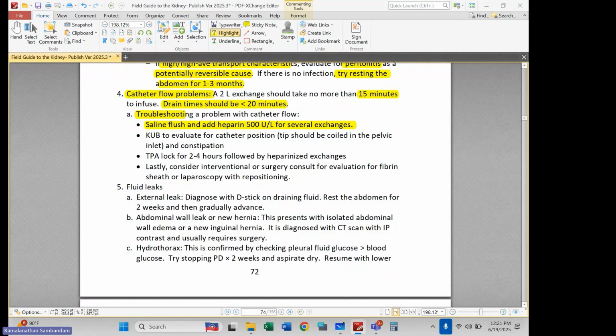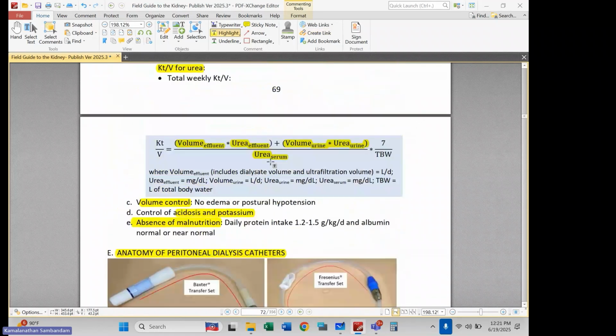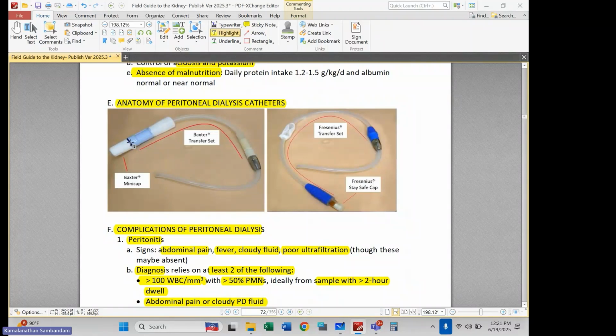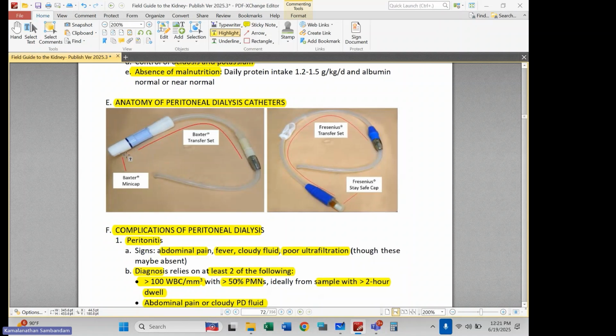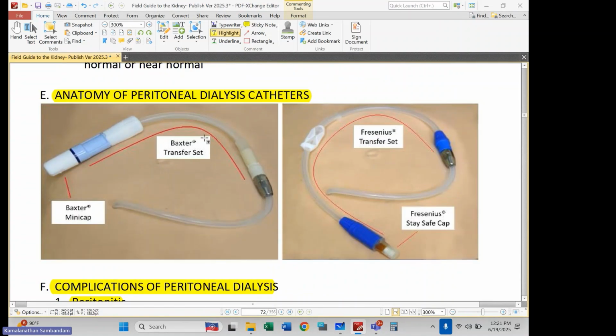Flush the catheter. That can usually be done with a simple Luer lock syringe, especially on that Baxter transfer set. Remember, this tip is compatible with a Luer lock syringe. So you'll just take off the mini cap. I'll use this terminology again just to reinforce familiarity with the apparatus. Take off the mini cap, connect to the tip with a Luer lock syringe, twist this in order to open the valve, and then you can power flush this catheter to get out any fibrin clots.